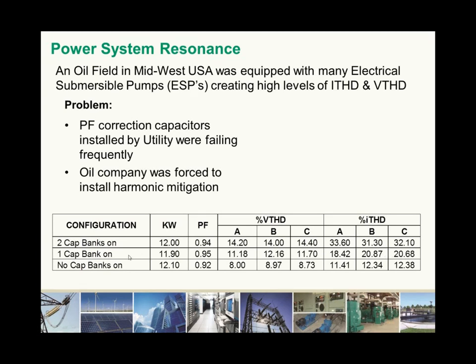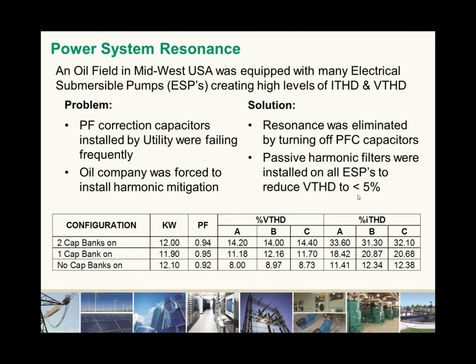When they turned off all the capacitor banks, it dropped to less than 9% voltage distortion, still higher than the 5% we want to see, but certainly much lower than our starting levels. And you can see there was very little impact to power factor, because the majority of the reactive power was harmonics. So we were able to convince the utility to keep the power factor correction capacitors off, and then we introduced harmonic filters on all the electrical submersible pumps to drop the current distortion further, lower the voltage distortion and improve the power factor.